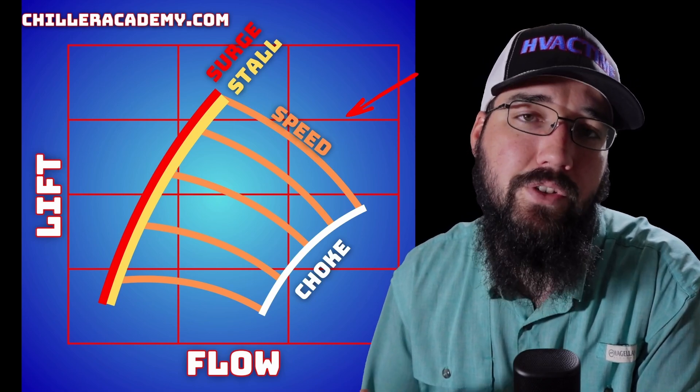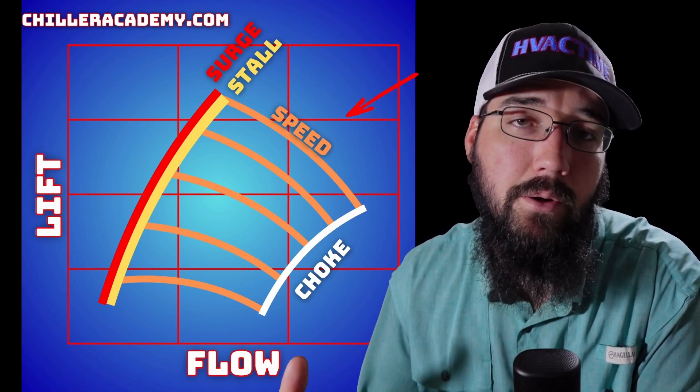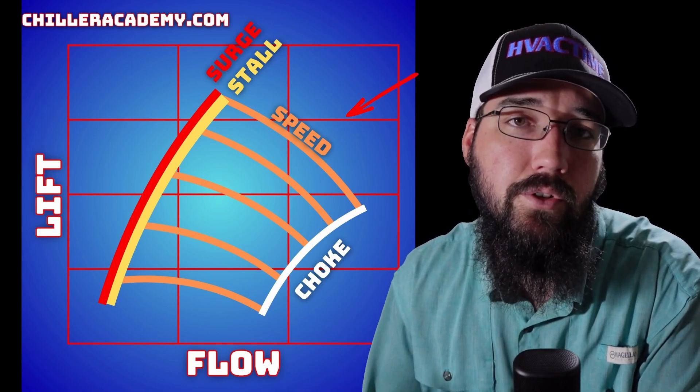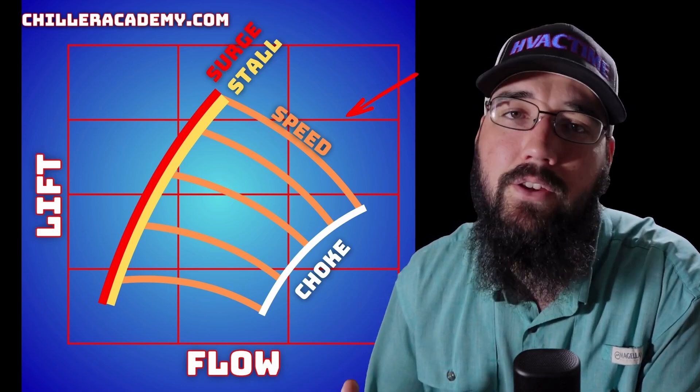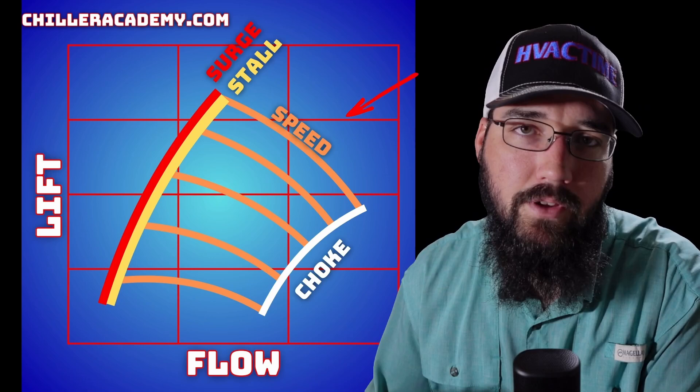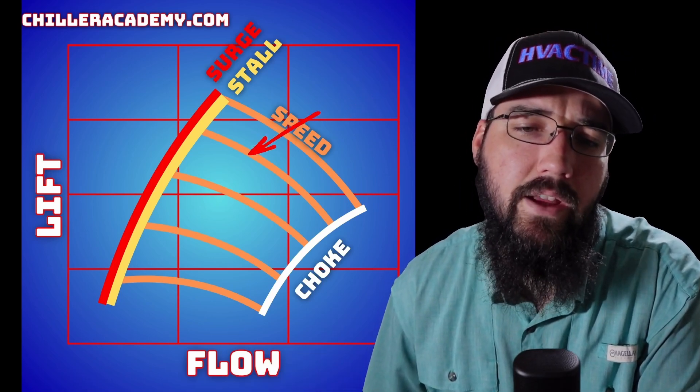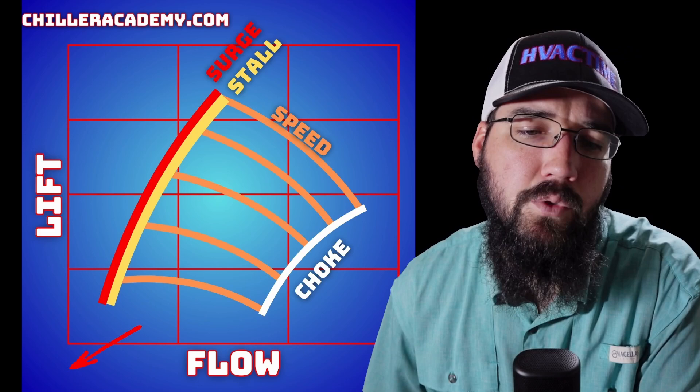Flow is how much volume is moving through our impeller. Another way to think about flow is what position are your IGVs, your inlet guide vanes, or if you're working on a York, a PRV, pre-rotation vane—they mean the same thing. So we have our graph here. This would be the lower end of it, and this is where your surge line is going to be, with a stall.